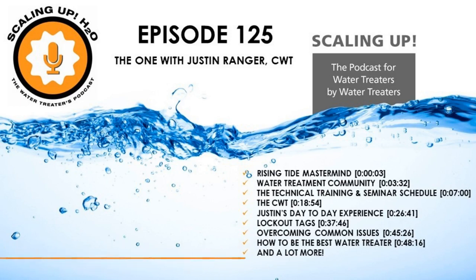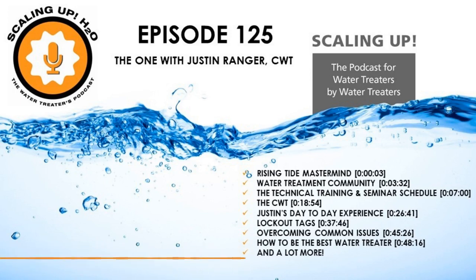I've seen some weird things over the years, like someone welding on the pressure vessel itself because a nipple was leaking on the side of the boiler, instead of fixing it properly. I've also seen pressure relief valves with plugs in them because they were leaking by, instead of replacing them or having a schedule to do so. Those are really serious and dangerous circumstances.